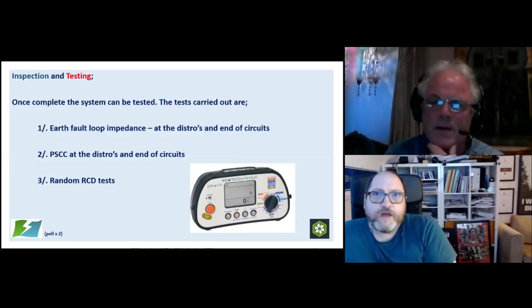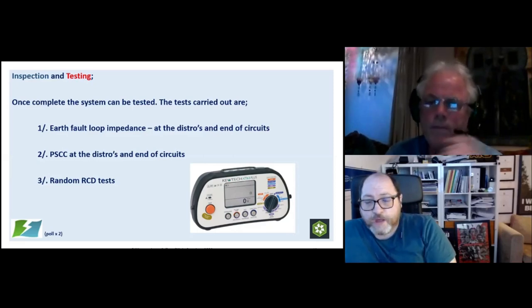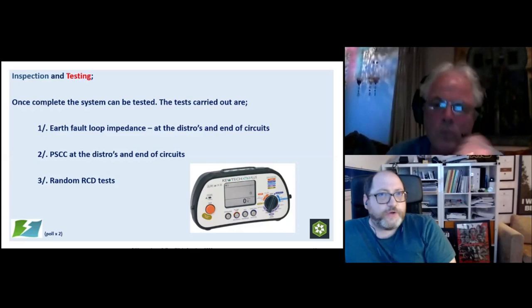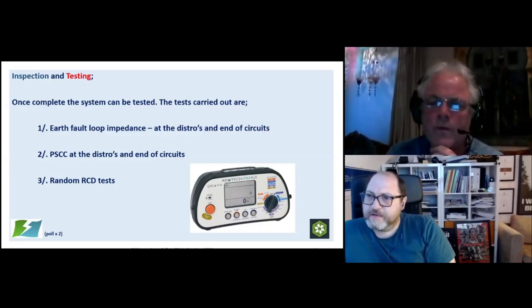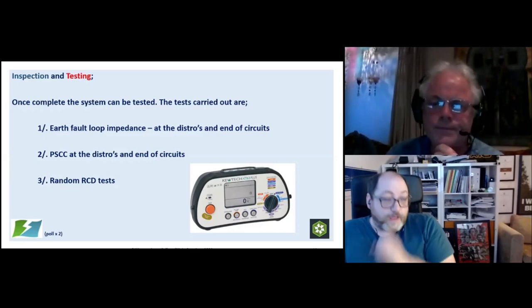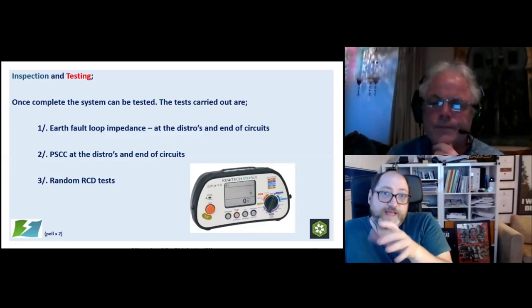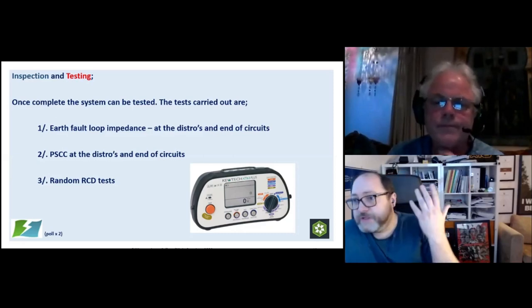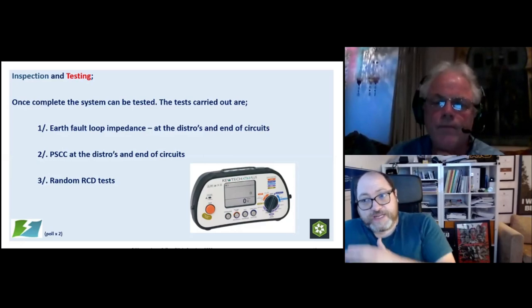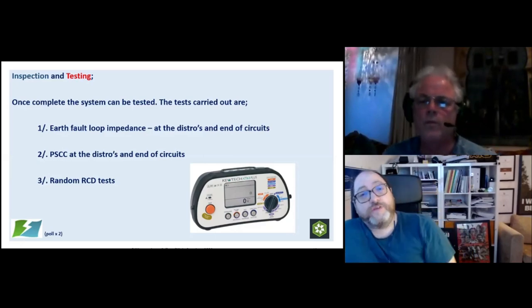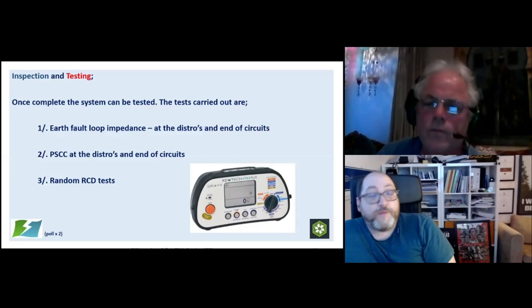Yeah. I did an EICR before Christmas, I think it was. And we had a circuit, radial circuit, 4mm and a C32, I think, which requires 320. And we had an amp measurement between line and neutral, something like 198, wasn't it? Right. 198 amps. Which, when we calculated the withstand formula to determine the length of time, it was too long. So the disconnection of the circuit would have been way too long, considering the temperature of the cable. Yeah. Right now in 7671.